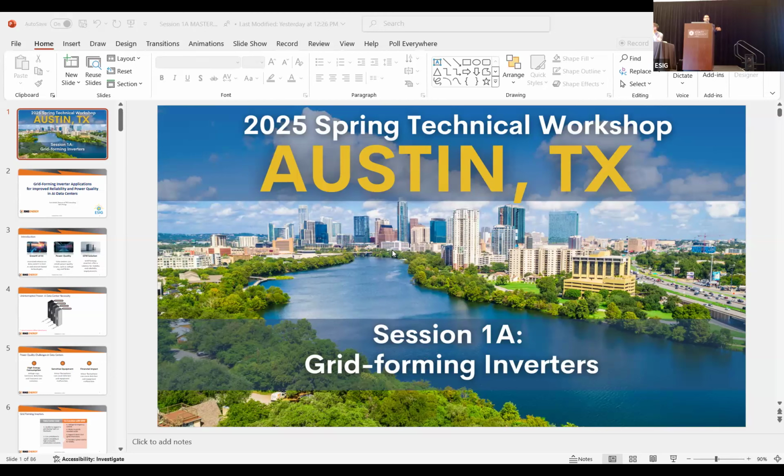And in that, we include GFM performance. We include the best known performance at the time. The other thing, we are not getting GFM completely out of the picture. In some projects, we considered implementing GFM because, again, in general, our grid is strong, but grid strength is relative to where you put it. If you don't position your IBR in the right location, you may end up in a situation where you need the GFM. So we assess that on a project by project basis.